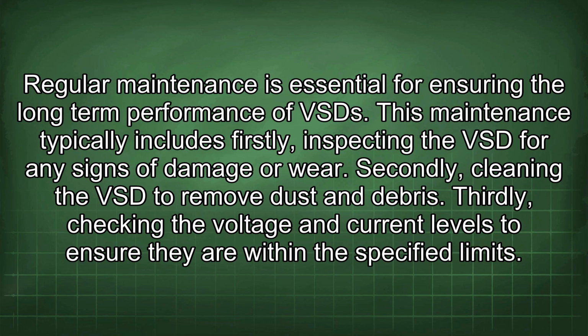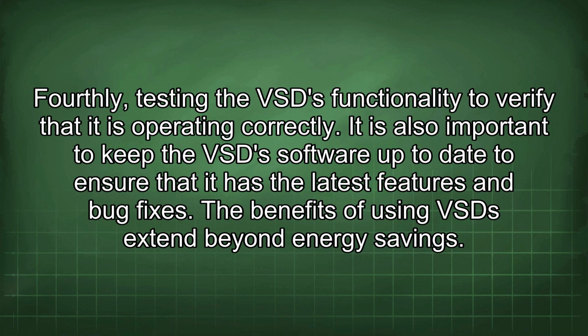This maintenance typically includes, firstly, inspecting the VSD for any signs of damage or wear. Secondly, cleaning the VSD to remove dust and debris. Thirdly, checking the voltage and current levels to ensure they are within the specified limits. Fourthly, testing the VSD functionality to verify that it is operating correctly. It is also important to keep the VSD software up to date to ensure that it has the latest features and bug fixes. The benefits of using VSD extend beyond energy savings.